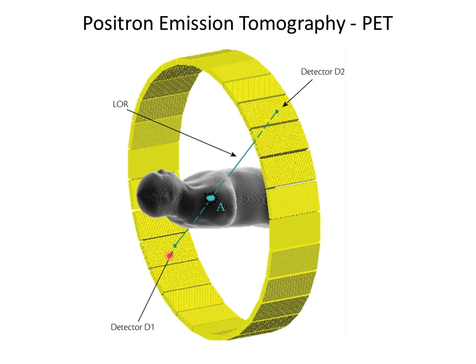If, for example, these detectors were fast enough, there would be a time delay between this detection and this detection if that event does not occur right at the center, right? If this distance is longer than this distance, this will hit first. So if you can measure in picoseconds, you can actually get some idea of how far along that line your event was. And modern CT or PET scanners actually can do that.